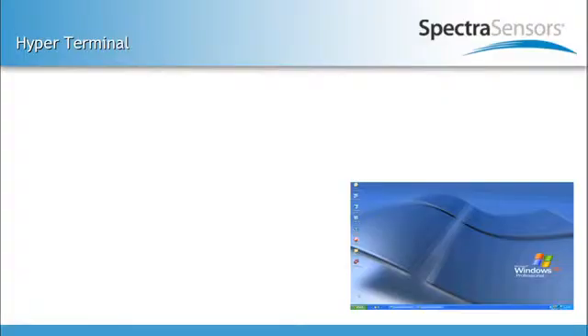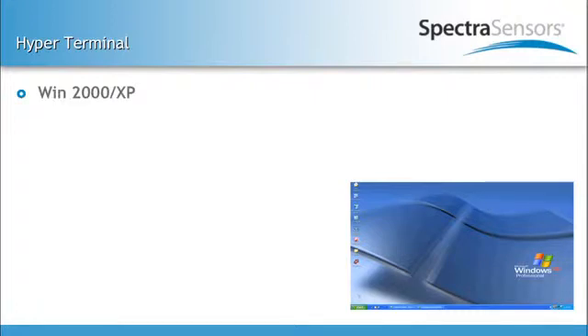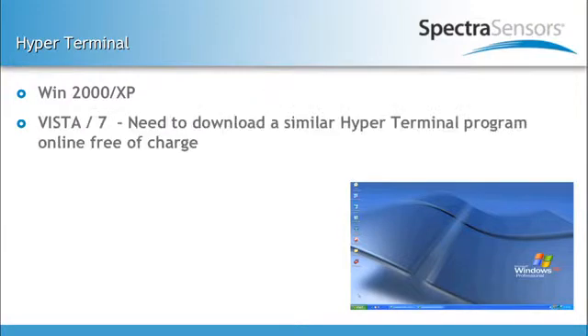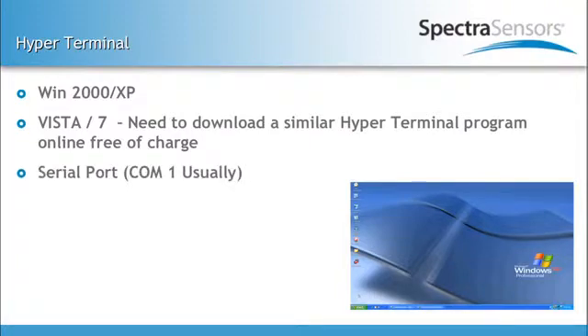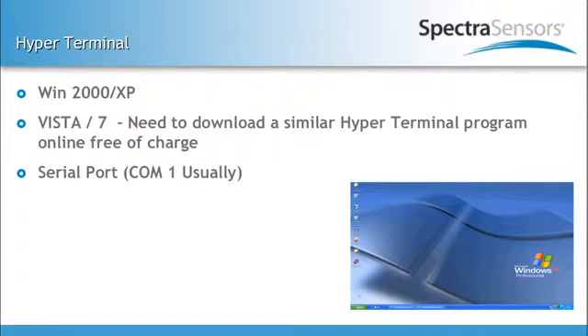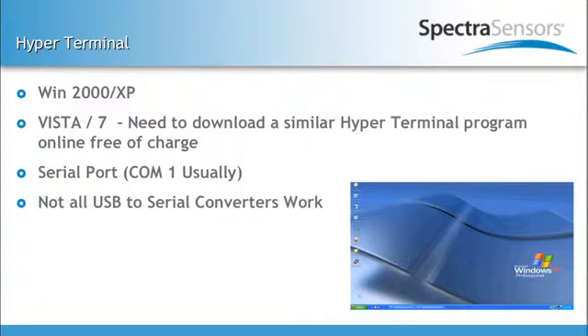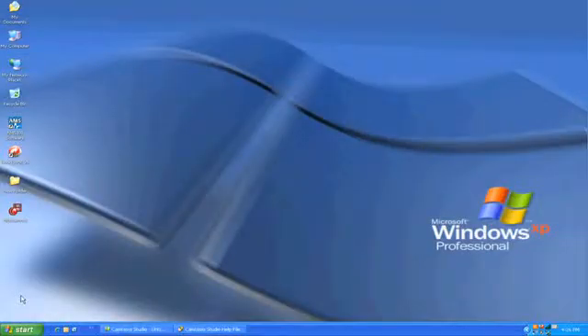In order to operate HyperTerminal, you would need to have a Windows 2000 or Windows XP operating system. If you have anything higher than that, like Windows Vista or Windows 7, you would need to download the HyperTerminal off the internet. The serial port of the laptop is usually labeled COM1. Now, if you don't have a serial port on your laptop and you're planning to use a USB to serial converter, you want to make sure that USB to serial converter works. Through our experience, not all of them do work. This procedure is the same for all three units.